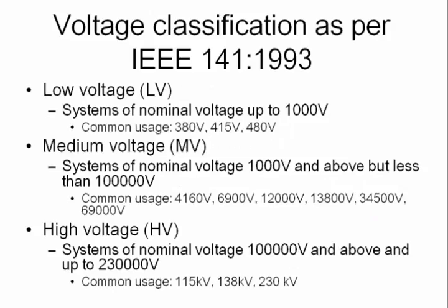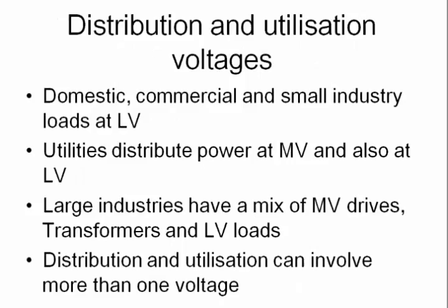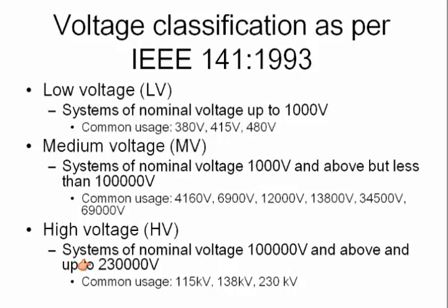In industrial terminology, which also follows from IEEE 141, low voltage is up to 1000 volts, so similar to the last one. But anything over is HV, but you have two groupings. Between 1000 volts and 100,000 volts, so 1 kV to 100 kV, it is medium voltage. Anything over 100 kV is high voltage, up to 230 kV. And anything over 230 kV is extra high voltage. So you have these further groupings. But technically, anything over 1000 volts is still high voltage.